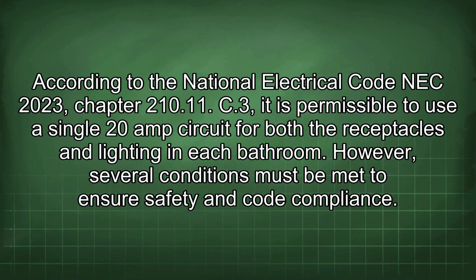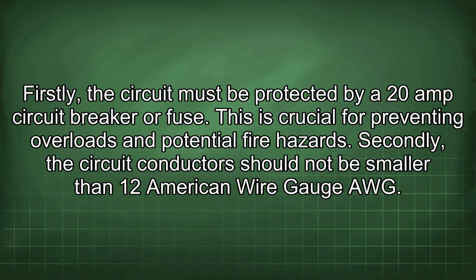According to the National Electrical Code NEC 2023, Chapter 210.11, C3, it is permissible to use a single 20-amp circuit for both the receptacles and lighting in each bathroom. However, several conditions must be met to ensure safety and code compliance. Firstly, the circuit must be protected by a 20-amp circuit breaker or fuse. This is crucial for preventing overloads and potential fire hazards.